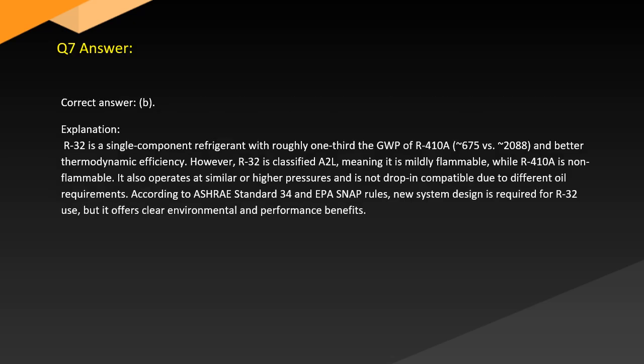Answer. Correct answer: B. Explanation. R32 is a single component refrigerant with roughly one-third the global warming potential of R-410A, 675 versus 2088, and better thermodynamic efficiency. However, R32 is classified A2L, meaning it is mildly flammable, while R-410A is non-flammable. It also operates at similar or higher pressures and is not drop-in compatible due to different oil requirements. According to ASHRAE Standard 34 and EPA SNAP rules, new system design is required for R32 use, but it offers clear environmental and performance benefits.